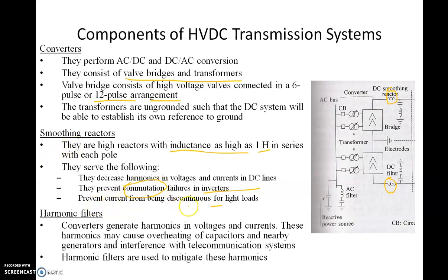The smoothing reactor also prevents current from being discontinuous for light loads. If the load is very light and the current is very low, the current can become discontinuous — it is present for some time, then becomes zero, then starts again. This is called discontinuous current. Since an inductor does not allow sudden change in current, the smoothing reactor keeps the current constant.